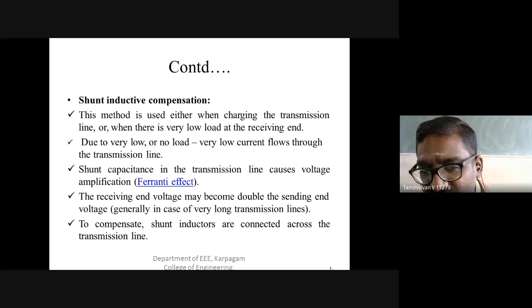Due to very low or no load, very low current flows in the transmission line. So the sending end voltage will be less compared to the receiving end, meaning the receiving end voltage will be more. This is called the ferranti effect, and it can be compensated with the help of shunt inductors connected across the transmission line.